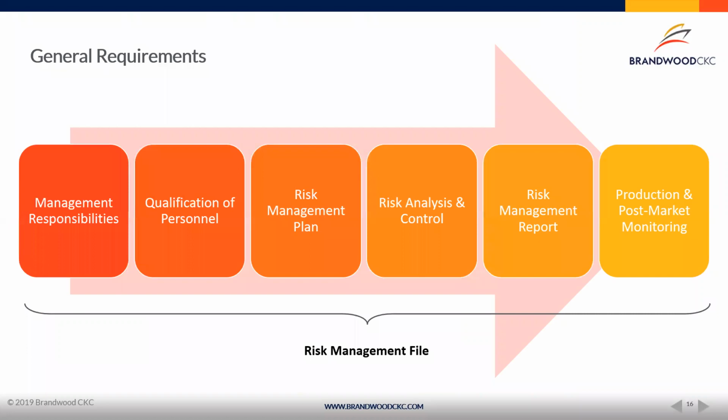So let's take a step back and talk about how we create a risk management file. After all, this is a documentation discussion, and how we, as a medical device manufacturer, put all of these things together. There are some general requirements to the risk management file. Again, I'm using the term risk management file as the entire file for documentation of risk assessment, management, and so on and so forth. So we start out with management responsibilities.